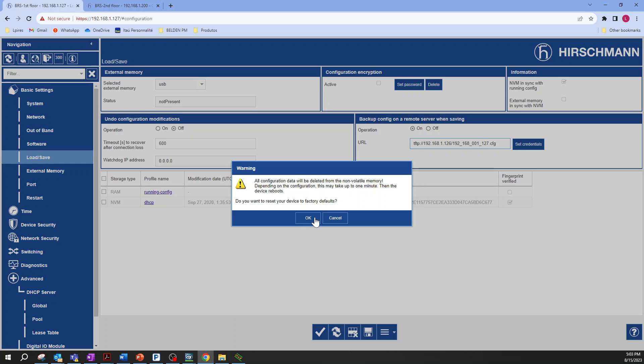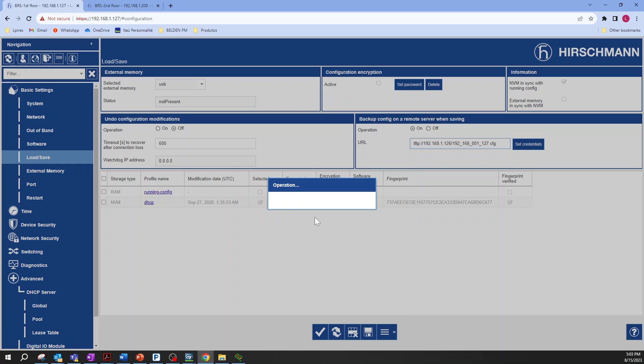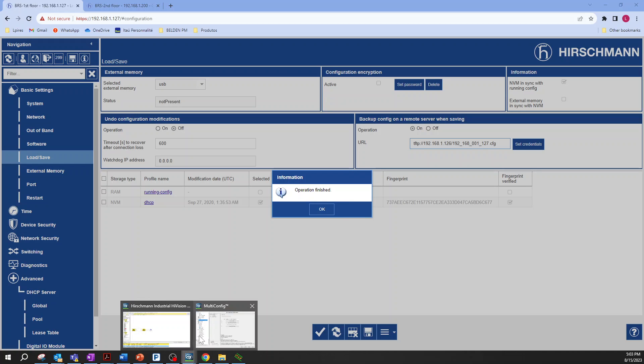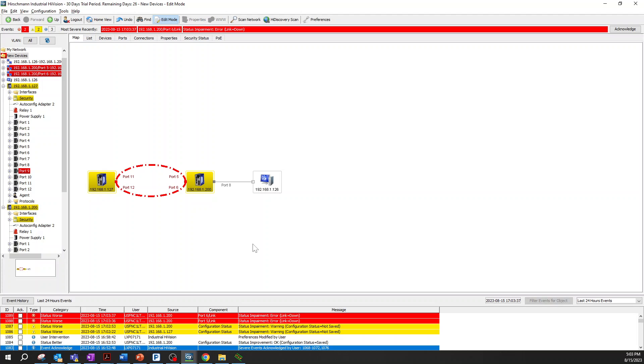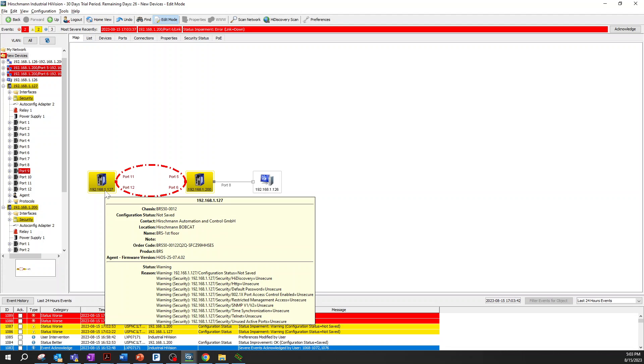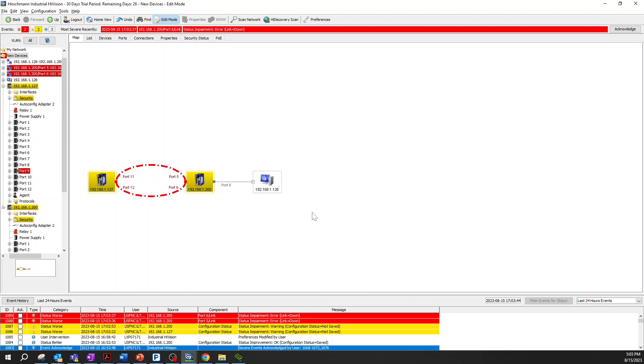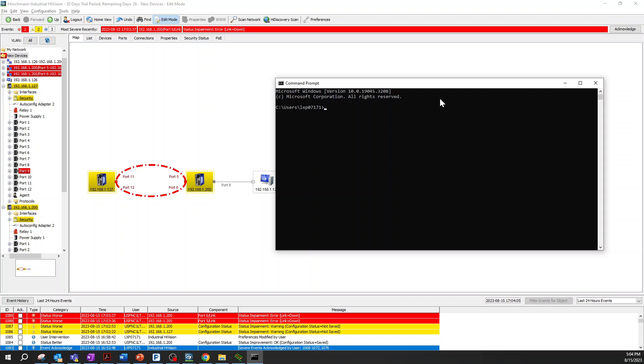You can see the device is on, both ports are connected. Let's pick the option back to factory. Do you want to reset your device to factory default? Yes. Operation finished. When you come back to Industrial HiVision, we are going to see the ports are down, the device will be unreachable soon. Once the device is rebooting, then this device will get back the previous configuration as per our configuration. Let's wait a few seconds and also let's take a look at the ping command. We can easily see when the device is back. Let's ping this device and wait a few seconds.